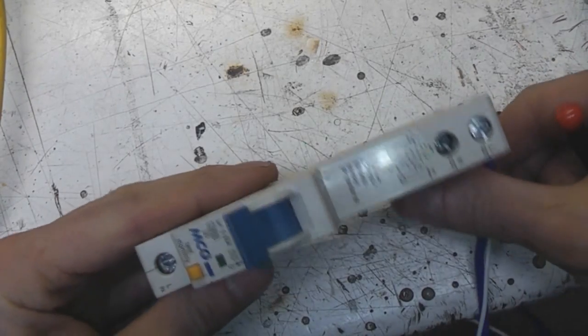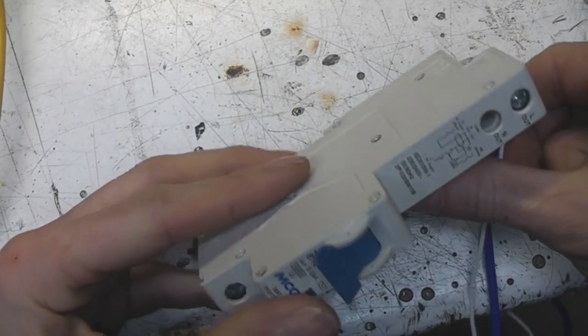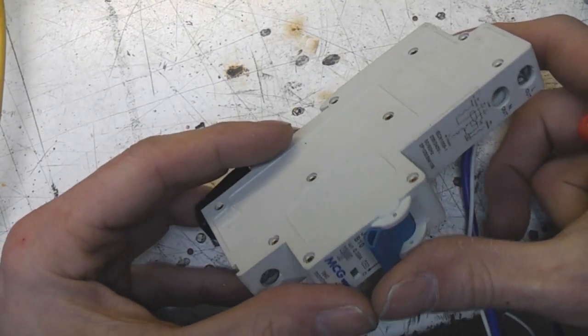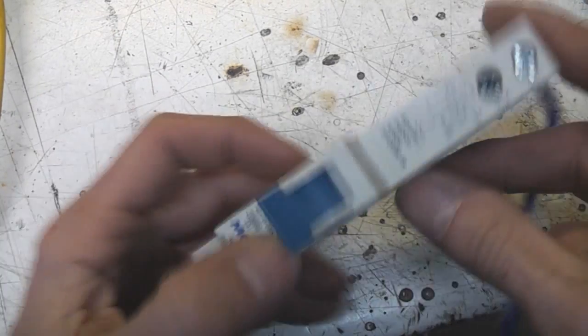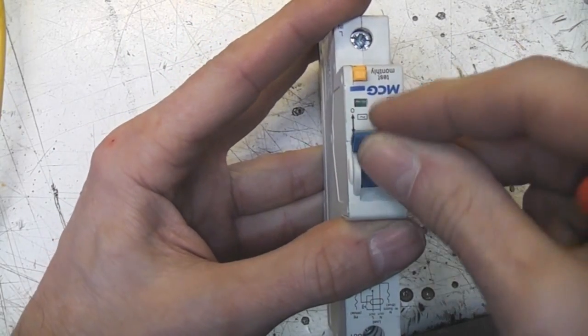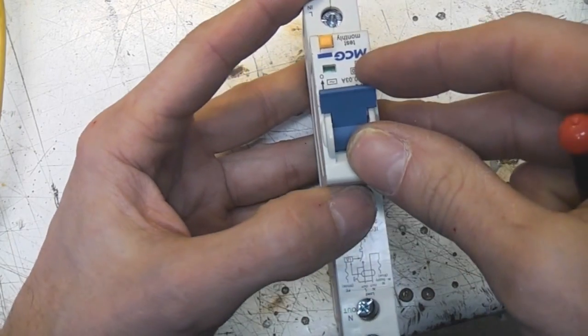Hi, today I was called out to do a bit of emergency fault finding on a lighting installation, somebody else's installation, not one of mine. And one of the problems was this was faulty. This is what we call in the UK an RCBO, which is a residual current circuit breaker with overcurrent protection.